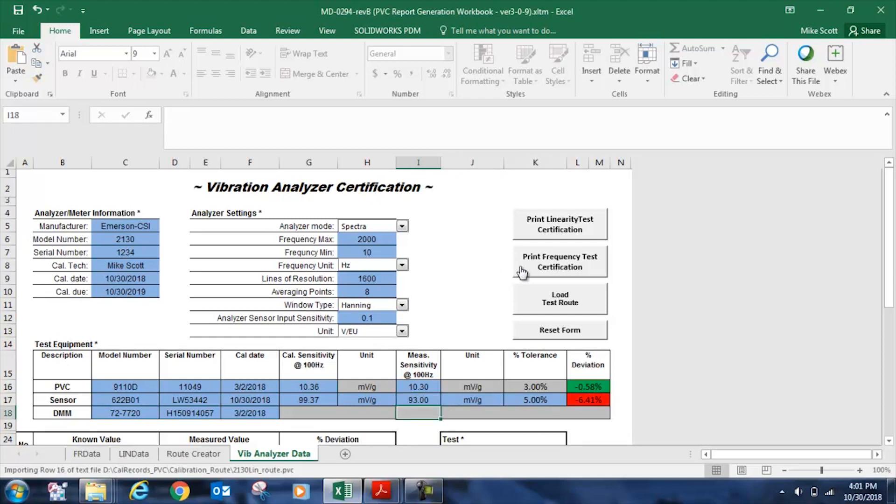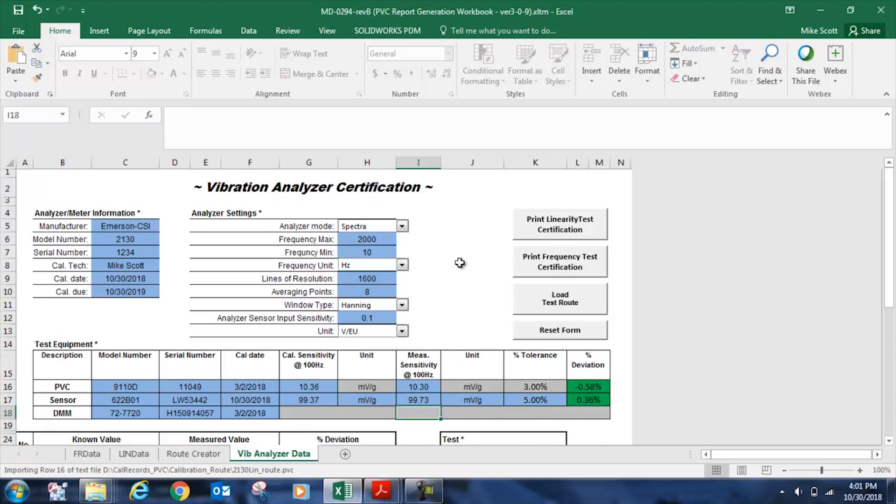the deviation cell would light up red because this deviation is greater than 5%, and that would let us know that we shouldn't be using this transducer for route-based predictive maintenance. But it tested at 99.73, so it's a good sensor for that purpose. And lastly, I've documented the model of my digital multimeter serial number and its last calibration date as well.